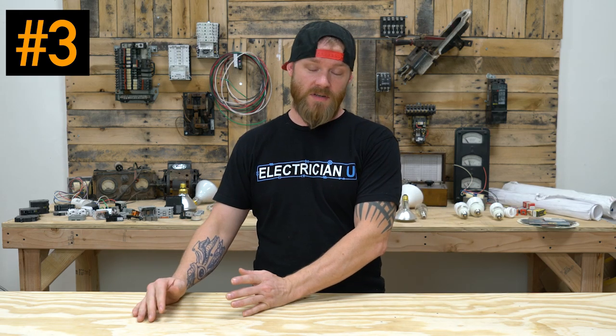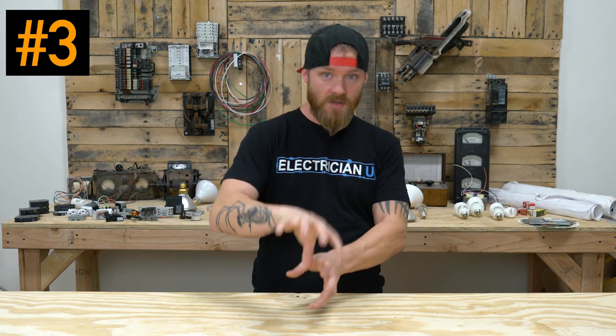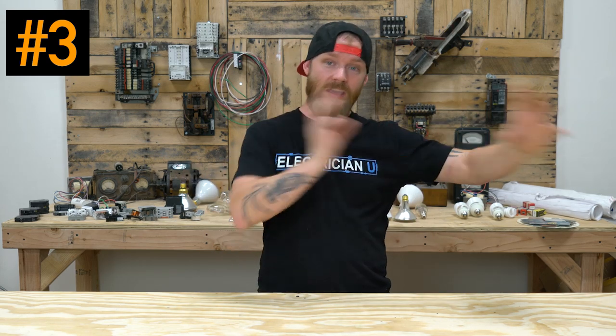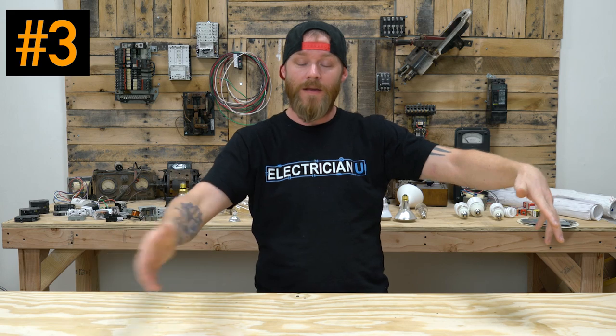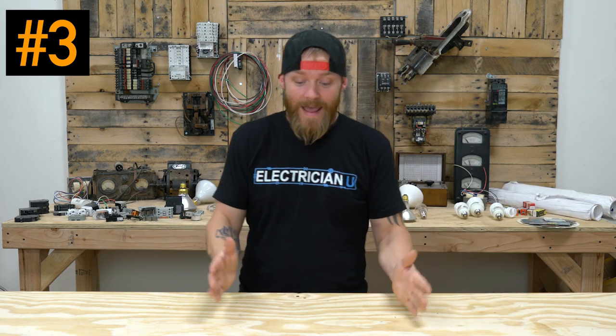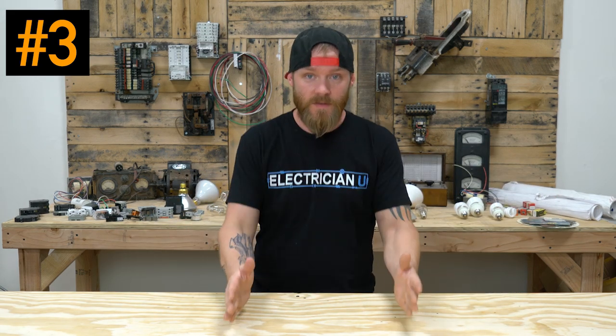Okay, the next one is feeders. Now feeders, a lot of people get confused on what this is. Feeders are not branch circuit conductors, and they're not service entrance conductors. Service entrance is at the beginning, to the service. Branch circuit is at the last panel, the final overcurrent device. From there on out, it branches out to devices. There's no other panel or breaker after that. Literally everything in between that is feeders.